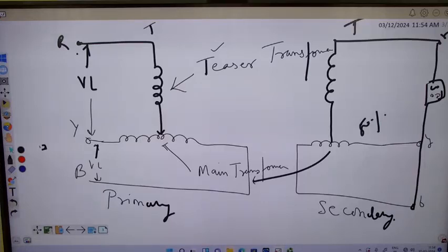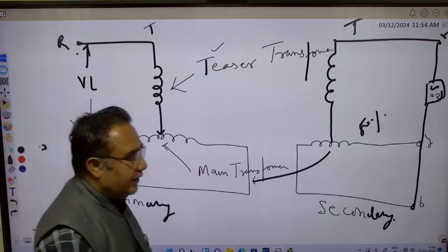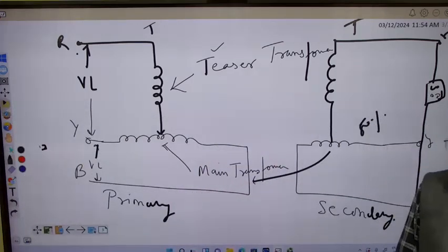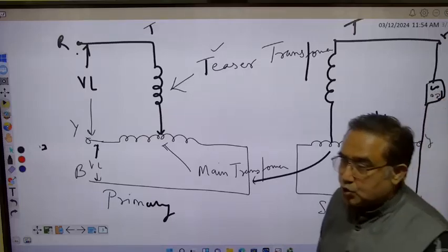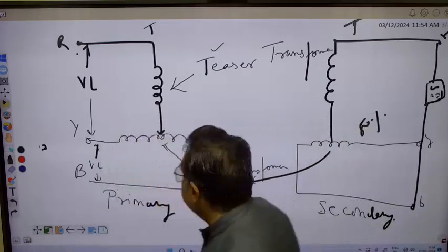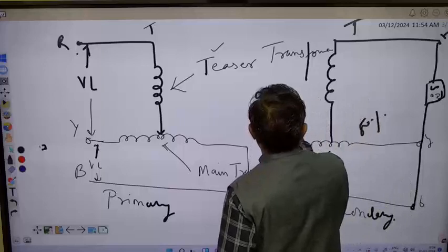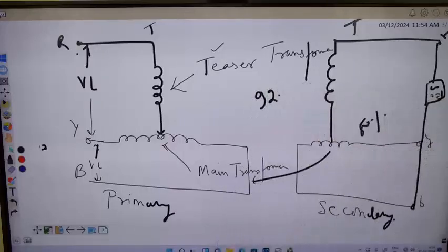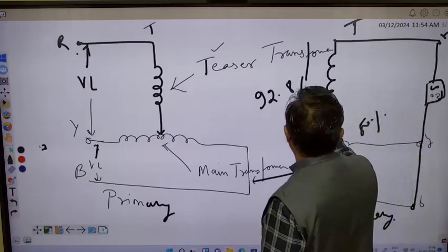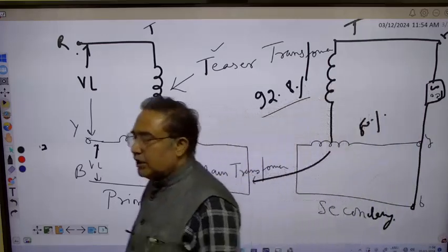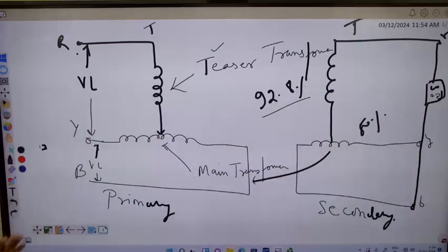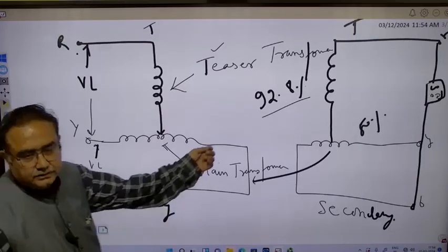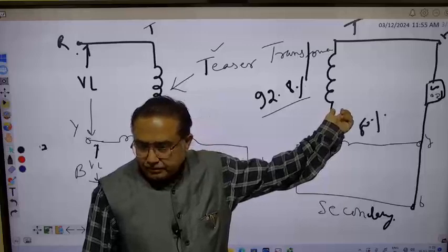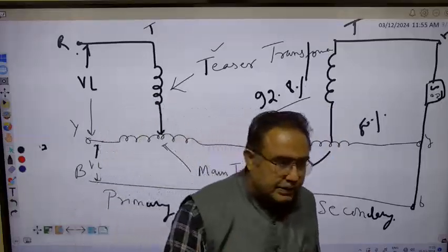No doubt, since only two windings are being used, the capacity will be reduced. In case of the VV connection, capacity was reduced to 57.7%. But here the beauty is that it will not reduce to that much extent. It will have a fair value, around 92.8%. You cannot load it with 100% load, but you can load it with 92.8% of its capacity.